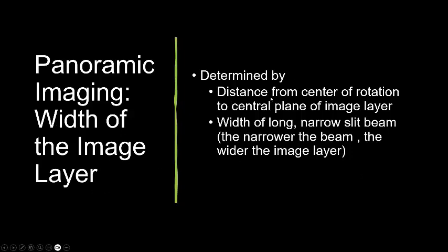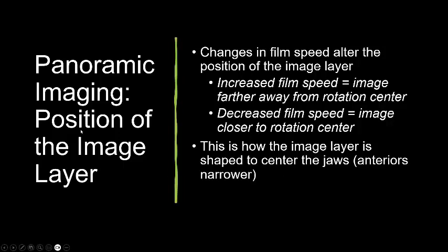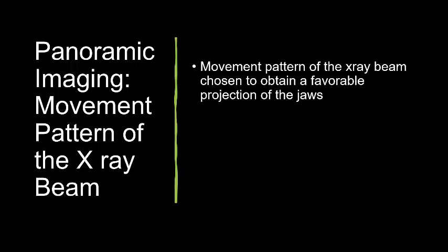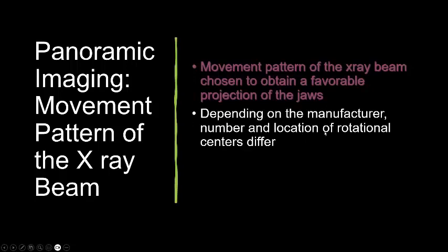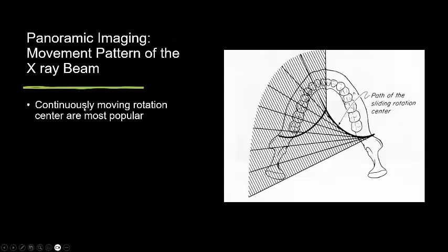The width of the image layer is determined by the distance from the center of rotation to the central plane of the image layer, and by the width of the long narrow slit beam — the narrower the beam, the wider the image layer. Regarding position: changes in film speed alter the position of the image layer. Increased film speed moves the image farther from the rotation center; decreased film speed moves it closer. The focal trough is narrow in the anterior region and wider in the posterior region. Continuously moving rotation centers are now most commonly used.